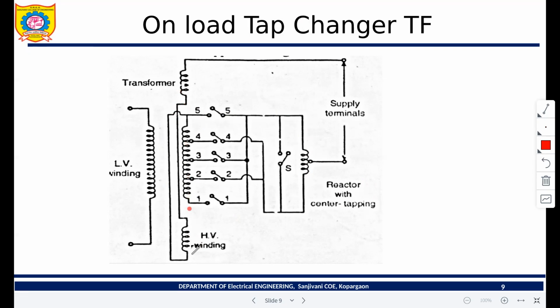These two transformer windings should be centrally tapped to this reactor, and this is the supply side terminal, or output we can get from this side. Now you can easily observe the construction point of view. I have explained all these points. Here, this reactor is used to avoid the short circuit of tappings, meaning when you switch on 1, then after that 2, then 3, this will avoid the short circuit. Now, how is the operation going to happen here?